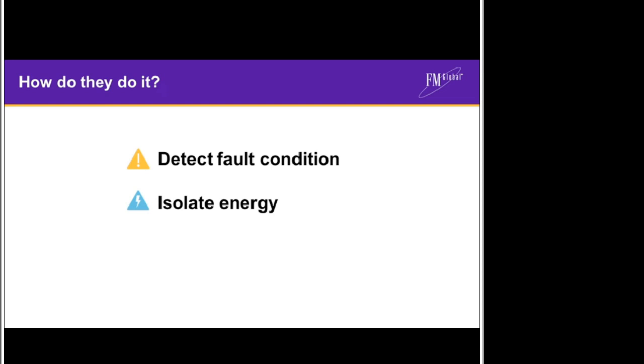Secondly, the safety devices need to react to that fault detection by isolating the energy from the turbine. The normal flow of energy in the turbine process is for high temperature, high pressure steam to bring kinetic energy into the system and for it to be converted into electrical energy, which is removed through the generator circuit breaker. A fault condition results in an imbalance between the input and the output energy. That energy needs to be dissipated somewhere, so the faster the energy coming into the machine can be isolated, the less damage the turbine will suffer.